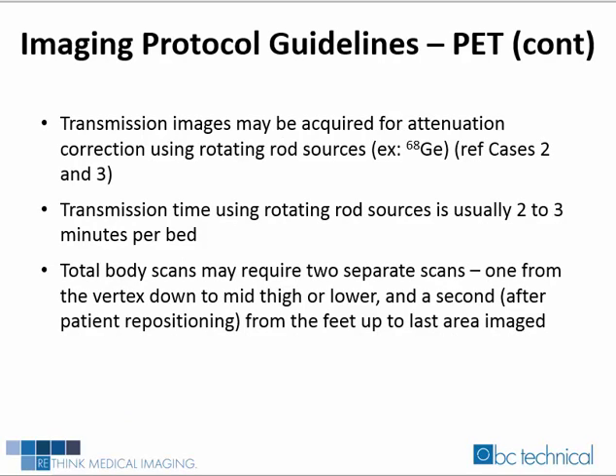Continuing with imaging protocol guidelines for the PET portion of the scan, transmission time using rotating rod sources is usually 2 to 3 minutes per bed. Total body scans may require two separate scans — one from the skull vertex down to mid-thigh or lower, and a second scan after patient repositioning from the feet up to the last area imaged. Currently, manufacturers have designed scanning systems that are now able to scan 2 meters or more in length, eliminating the need to reposition patients requiring a total body scan.